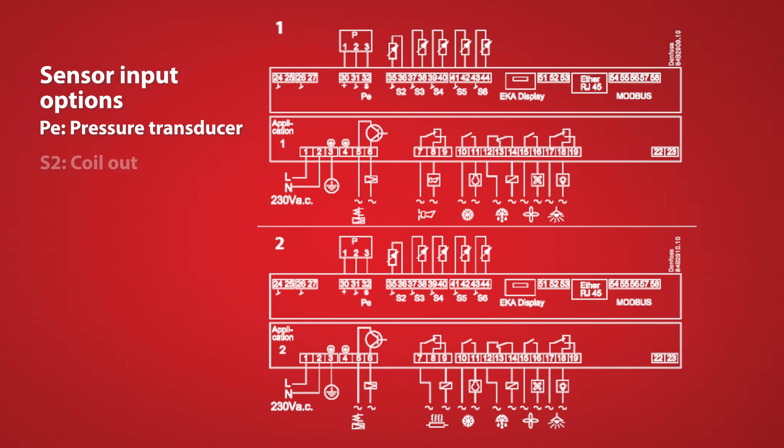Going down the line we have the S2 sensor which is the coil out temp sensor. The next sensor is optional. It's the S3 sensor which is a return air sensor. This is needed if you want to do adaptive defrost.